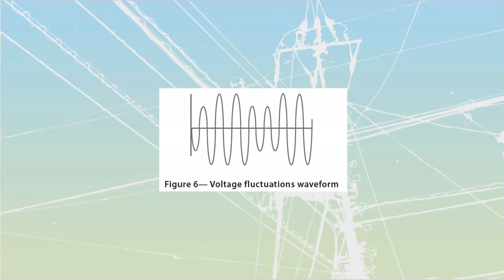Voltage fluctuations happen when the voltage itself is changing, going a little high, going a little low, etc. This can be caused by all sorts of things, usually switching operations, or certain types of loads connected that have a cyclical operation, where it's going to pull current, then not pull current, then pull current again, and so on. They give the example of arc furnaces, where arcs are established and shut off to create massive amounts of heat. Those types of loads give us voltage fluctuations.